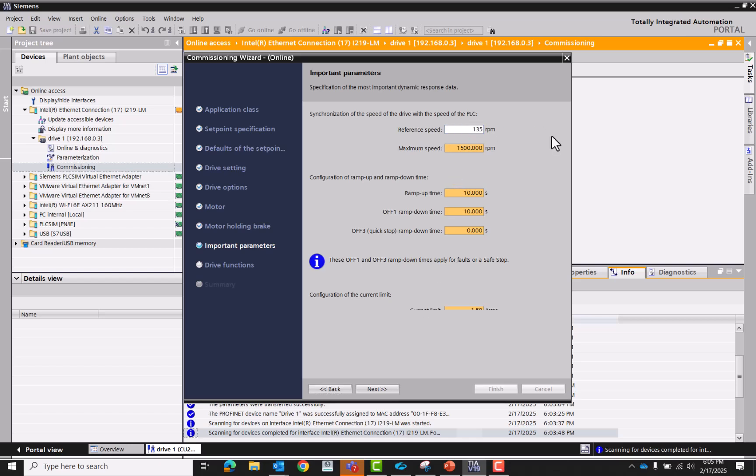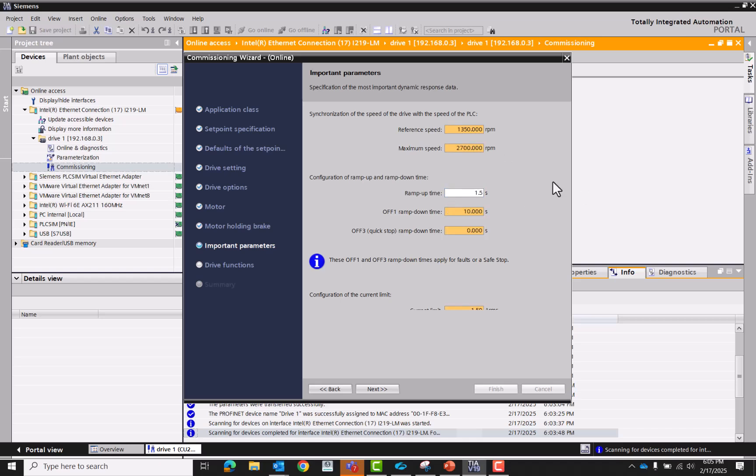Reference speed is max RPM of the motor. The max speed that we want the motor run out, we can do twice, right? So at 2700. Ramp time, do 3 second ramp time.